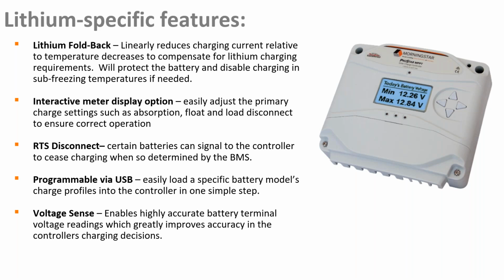One of the access points that we provide is actually our RTS terminals, which would be for the remote temperature sensor. Typically, you're not going to be having temperature compensated charging with lithium batteries, but you can still use the RTS terminals connected to that dry contact, so that when the BMS trips on alarm or some low voltage condition, it can signal to the controller to turn off or stop charging. So that's a pretty nice application as well.